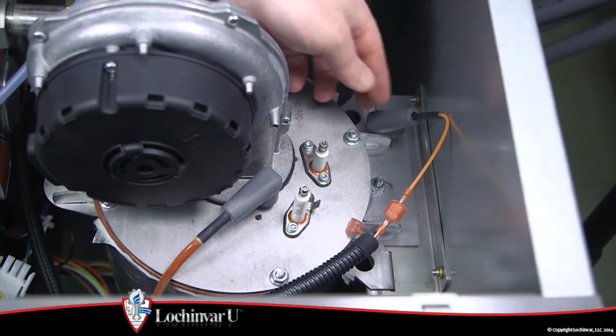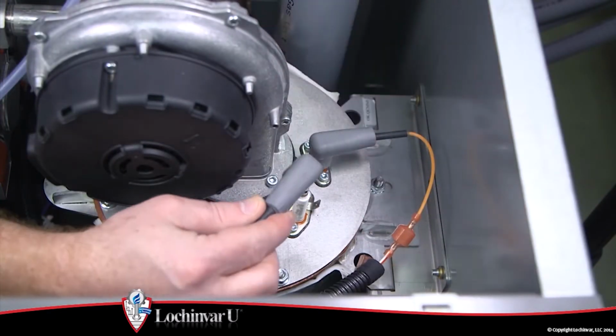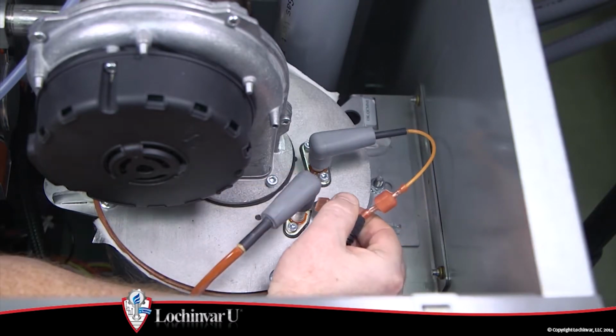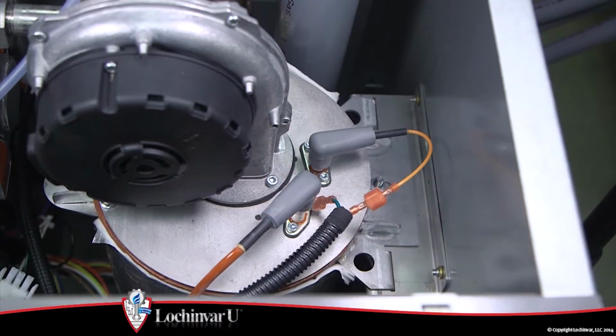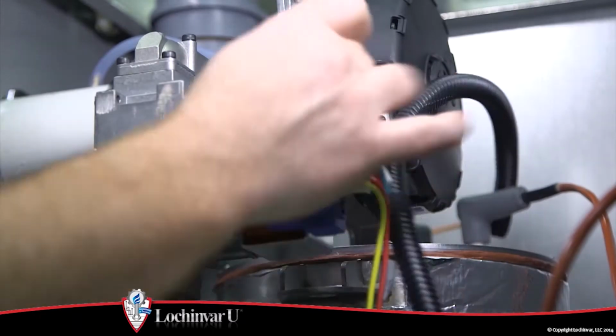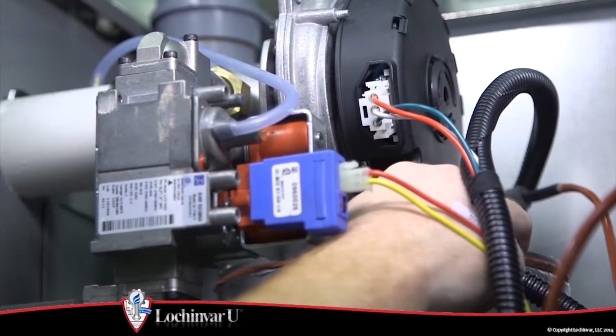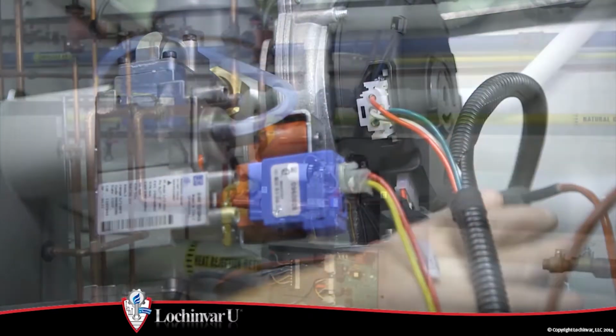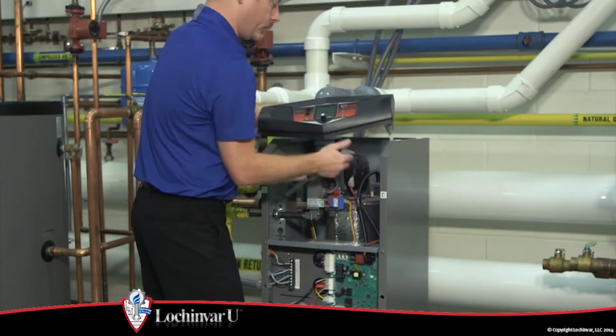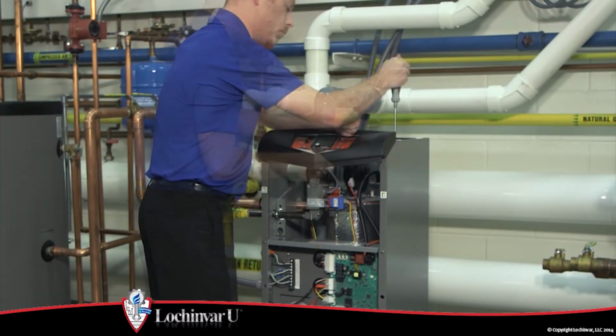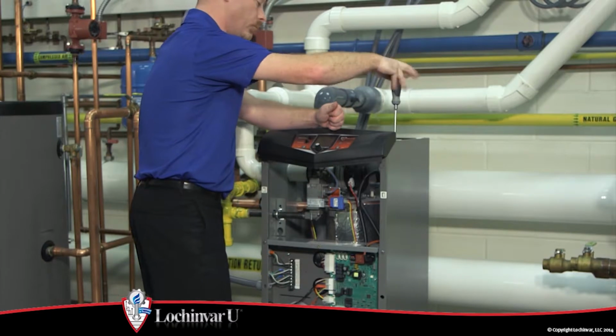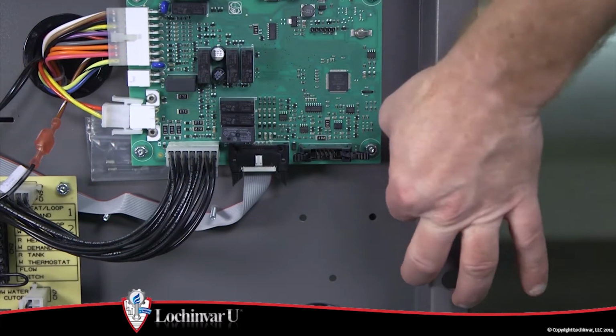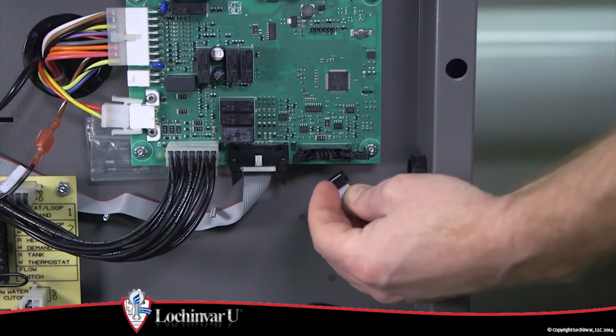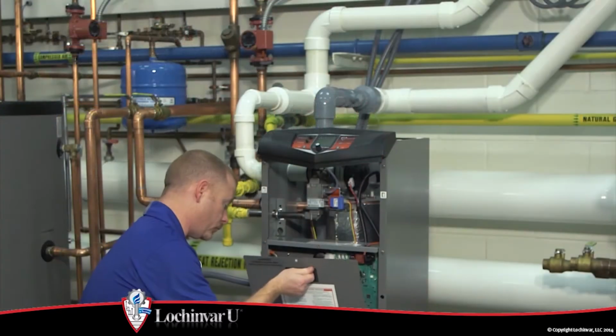Reconnect the wiring from the flame rod, spark igniter, and ground terminals to the heat exchanger door, and reconnect the 2 wiring harness connections to the combustion blower. Now replace the bezel to the front of the unit, and install and tighten the 4 screws securing the bezel. Now reconnect the ribbon cable from the display to the main control board.